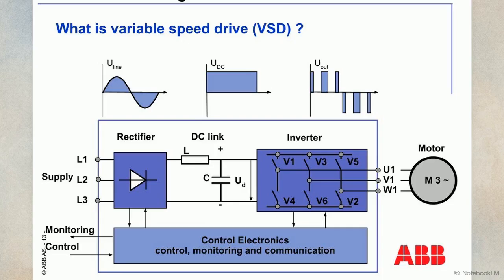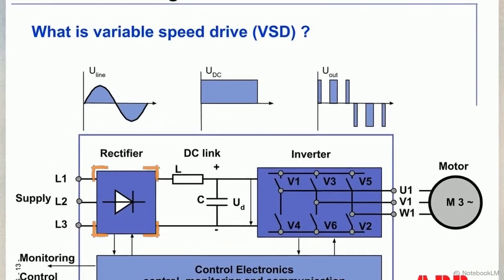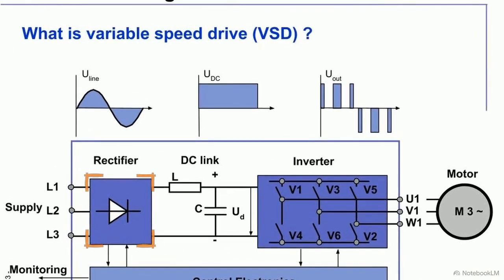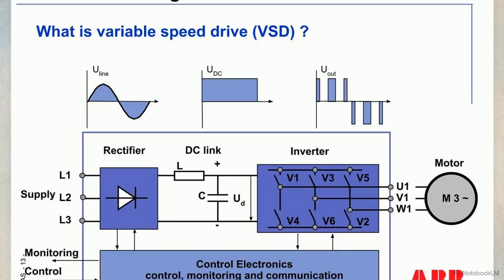This diagram shows the internal architecture of a variable speed drive. Stage 1 is the rectifier. This diode bridge receives the fixed frequency AC from the transformer and converts it into a pulsating direct current. Stage 2 is the DC link. A bank of capacitors smooths that pulsating DC into a perfectly flat, stable DC bus. This link severs the connection between the ship's fixed grid and the motor's ultimate speed.